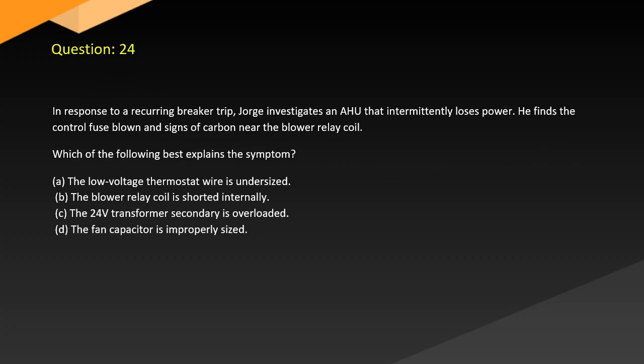Question 24. In response to a recurring breaker trip, Jorge investigates an AHU that intermittently loses power. He finds the control fuse blown and signs of carbon near the blower relay coil. Which of the following best explains the symptom? A. The low-voltage thermostat wire is undersized. B. The blower relay coil is shorted internally. C. The 24-volt transformer secondary is overloaded. D. The fan capacitor is improperly sized.